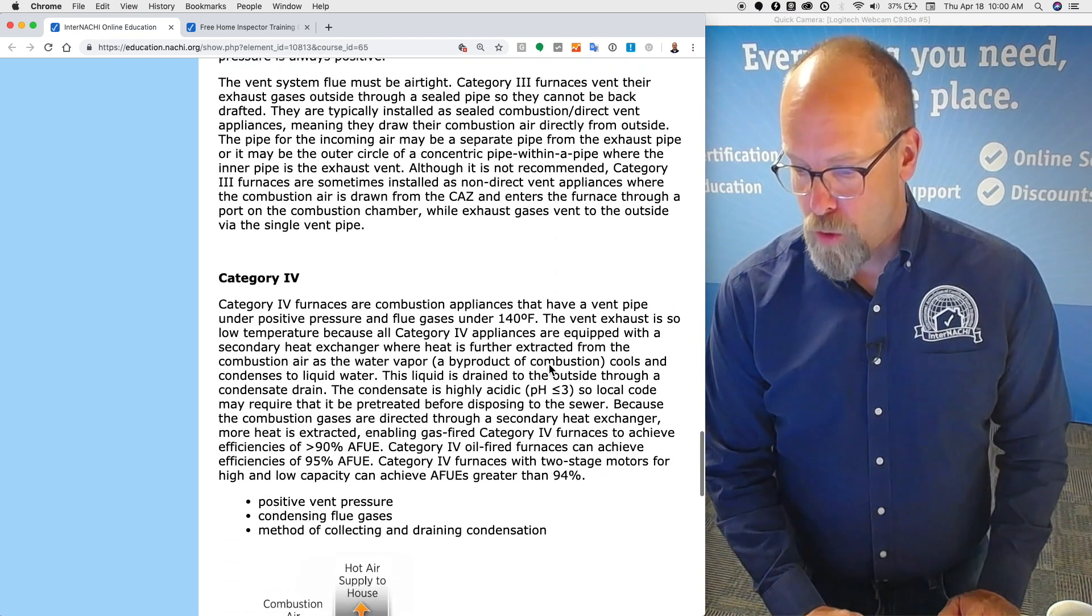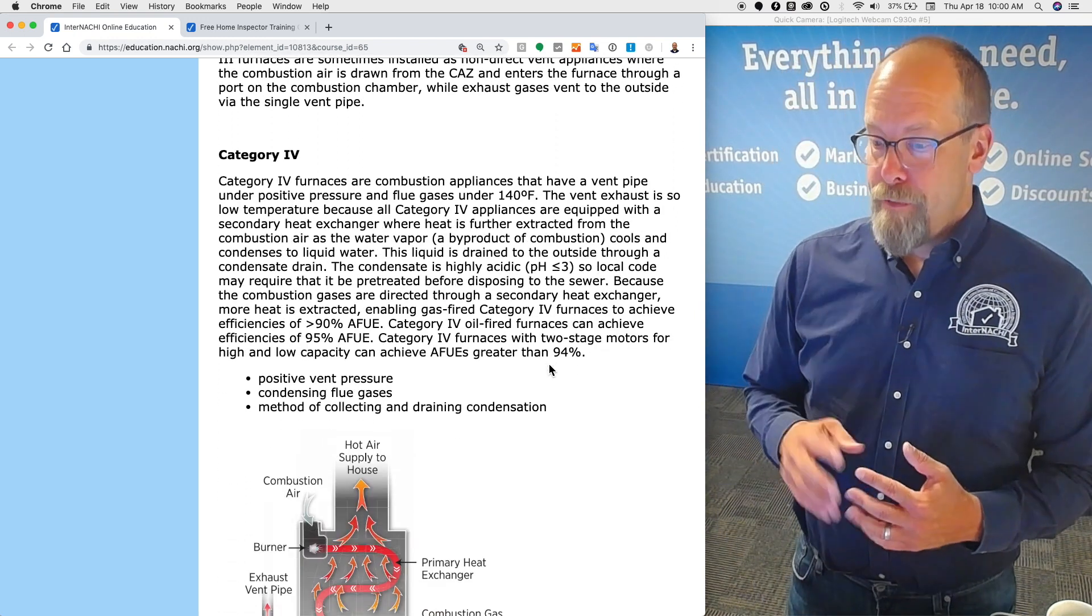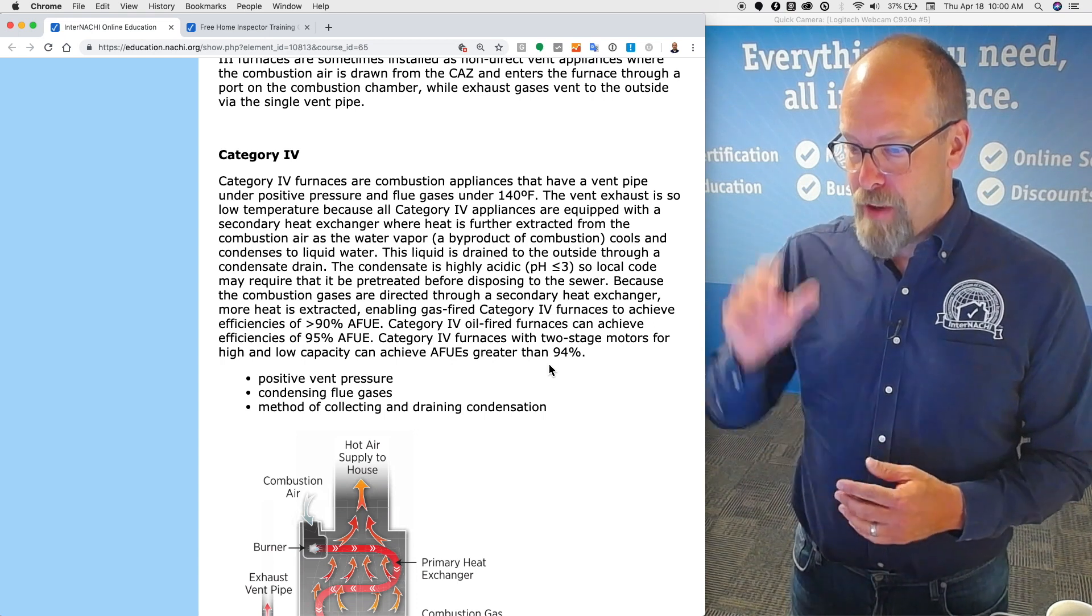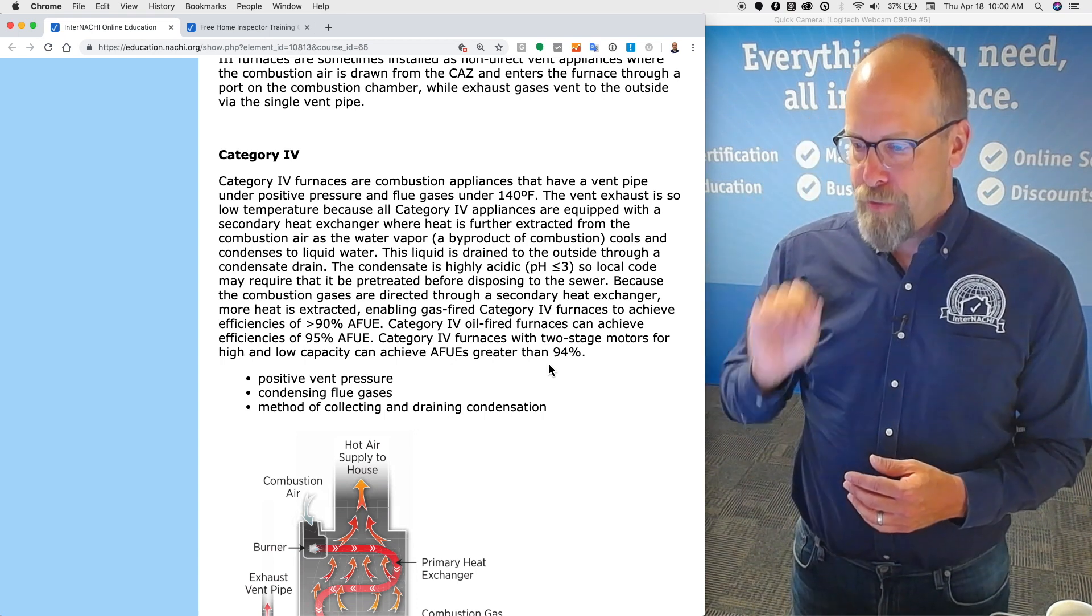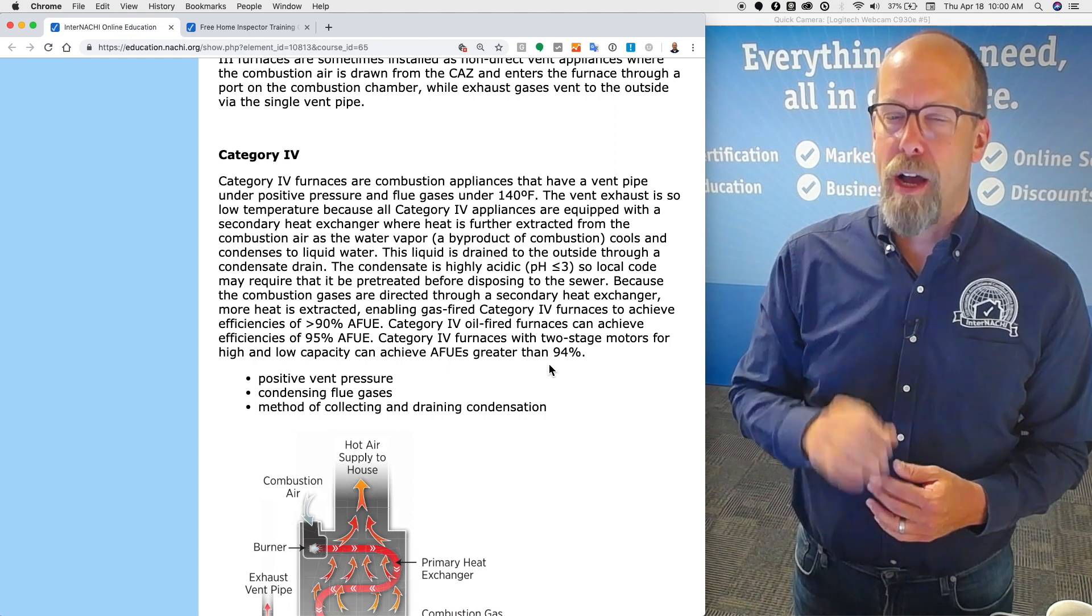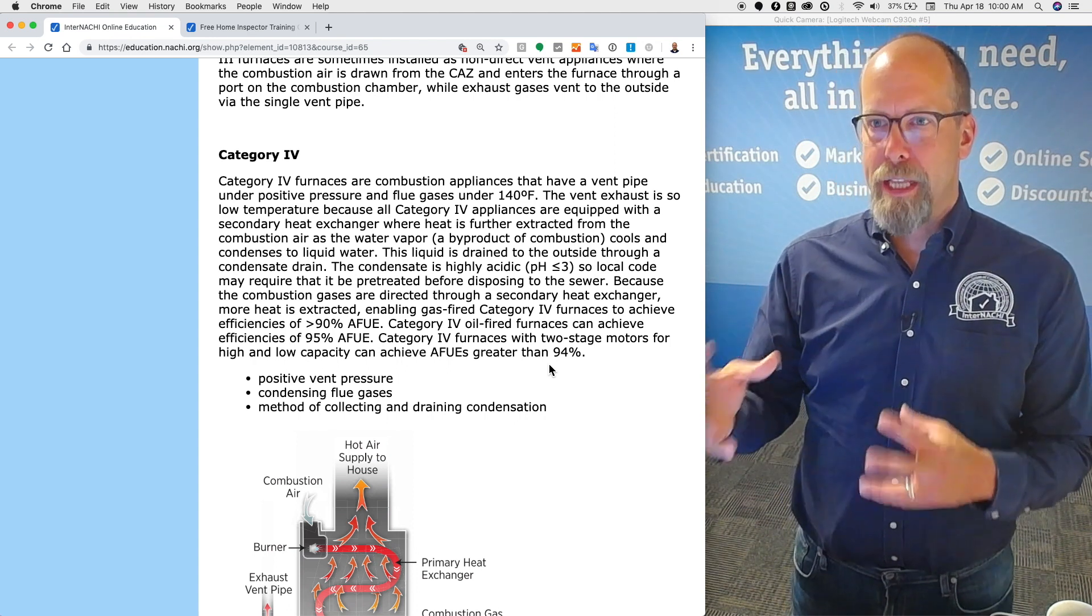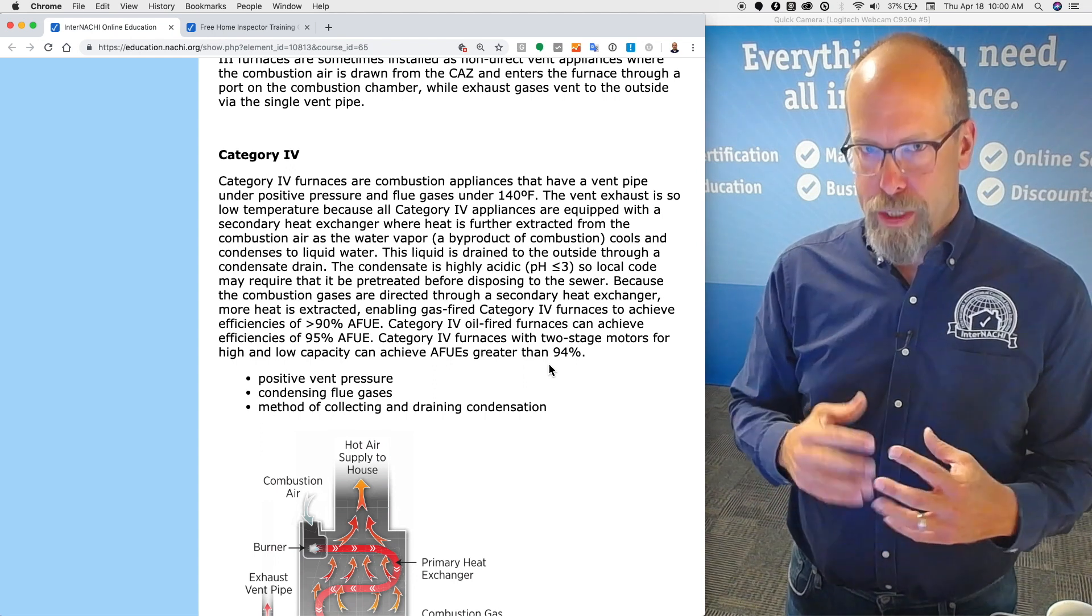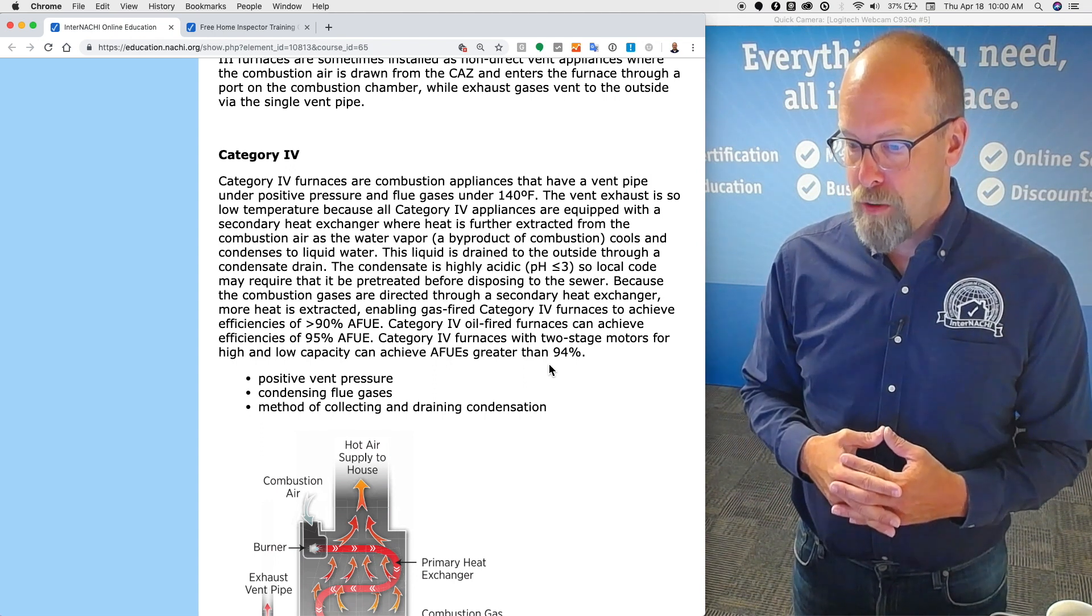Let's go to category four. Category four furnaces are combustion appliances that have a vent pipe under positive pressure and flue gases under 140 degrees Fahrenheit. So positive pressure in the pipe and low temperatures. The vent exhaust is so low because all category four appliances are equipped with a secondary heat exchanger.